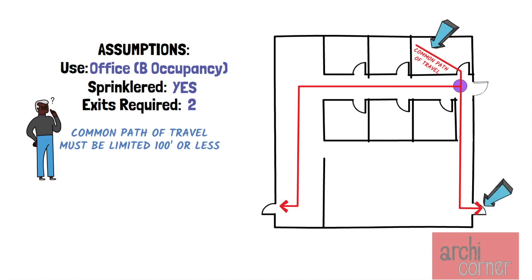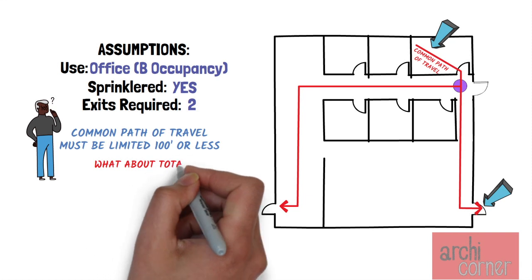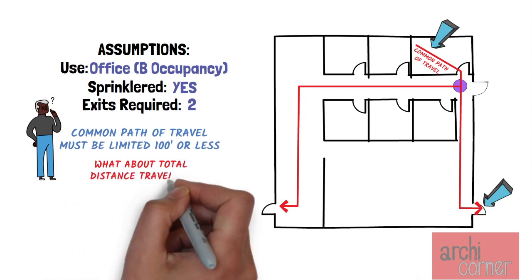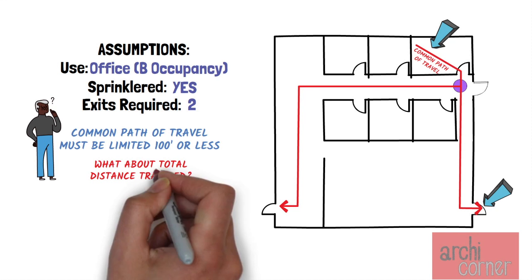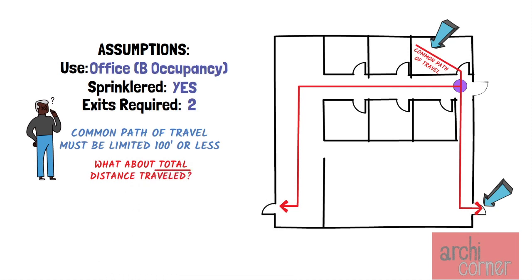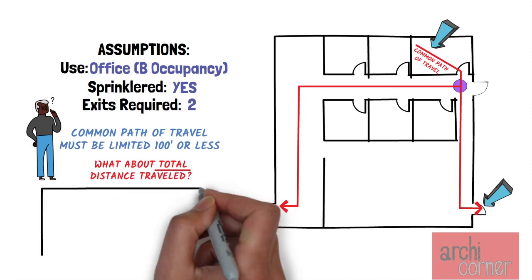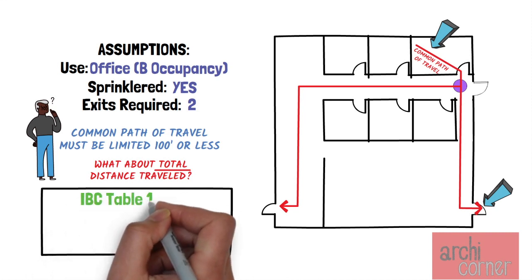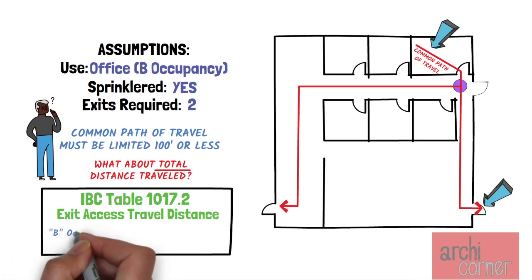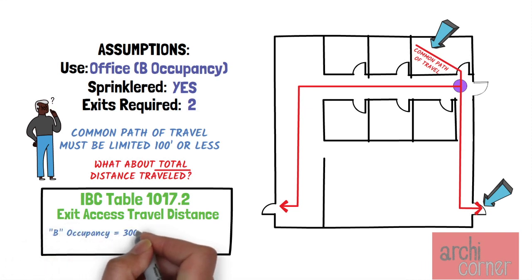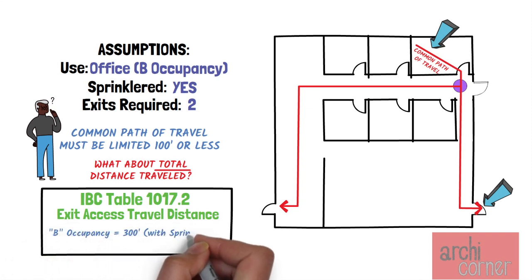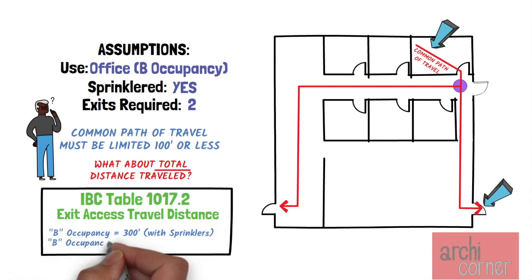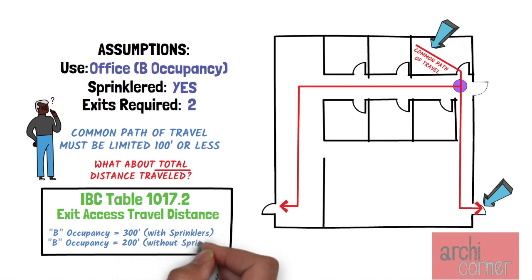We have discussed the issue of common path of travel, but what about the rest of the path of travel? Is there a limitation to the total distance traveled? The total distance traveled is limited to the distances noted in IBC Table 1017.2, which for an office is limited to 300 feet if the building is sprinklered. If the building is not sprinklered, the total travel distance would be limited to 200 feet.